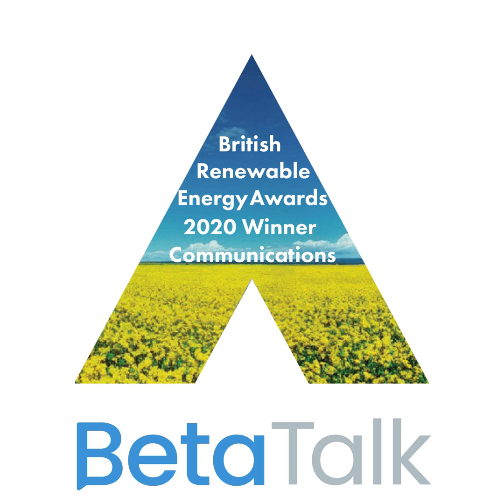So we started with the concept of a flexible heat pump using our tech, and that developed into our standard Hummingbird heat pump, which is essentially a 4 or 5 kilowatt rated thermal output heat pump, all in the size of about a desktop PC. So it's about this, and it weighs about 25 kilos in total. And you can couple either with a water source or an air source. I call it water source or air source, I don't mean it's actually using a refrigerant. I mean, it's either a fan coil unit for your air source or a water loop for your water source. So it's trying to be as flexible as possible.